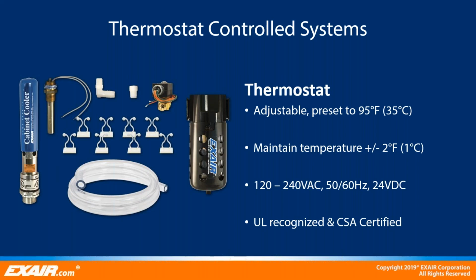It's rated for 120 to 240 volt AC or 24 volt DC. The thermostats are UL recognized and CSA certified. They are not position sensitive, but should be located in a hot area inside the enclosure through a 7/8 knockout through the enclosure wall or on a bracket inside the panel.